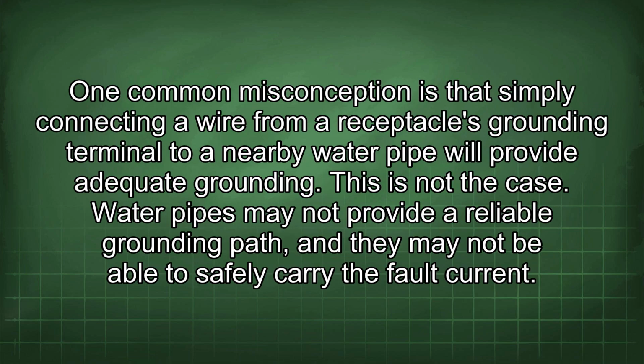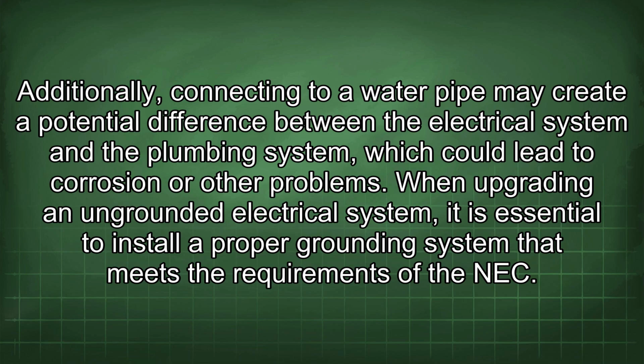One common misconception is that simply connecting a wire from a receptacle's grounding terminal to a nearby water pipe will provide adequate grounding. This is not the case. Water pipes may not provide a reliable grounding path, and they may not be able to safely carry the fault current. Additionally, connecting to a water pipe may create a potential difference between the electrical system and the plumbing system, which could lead to corrosion or other problems.